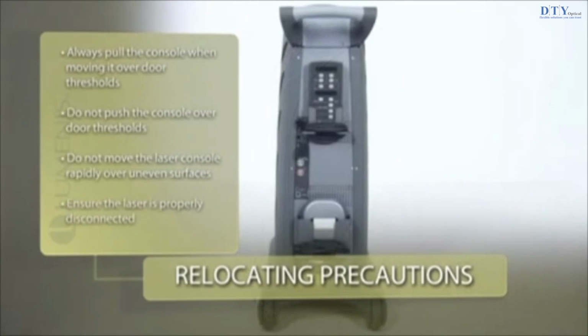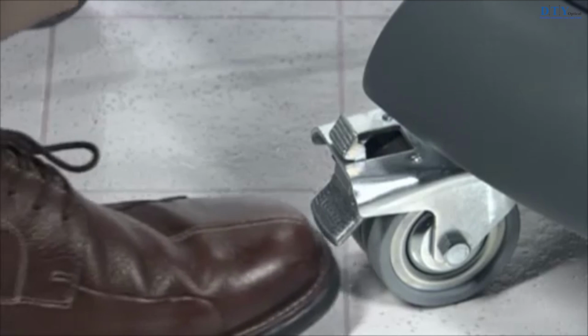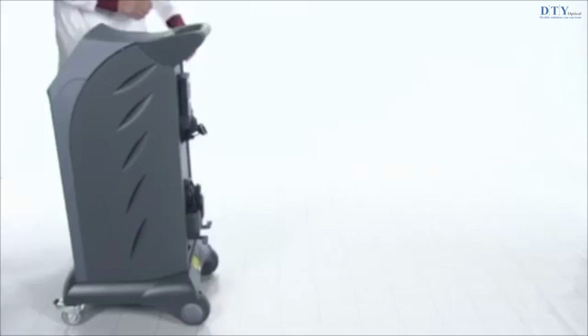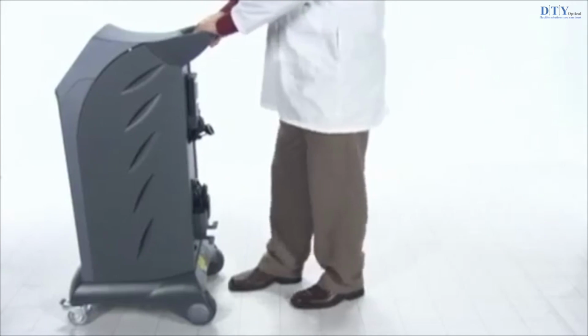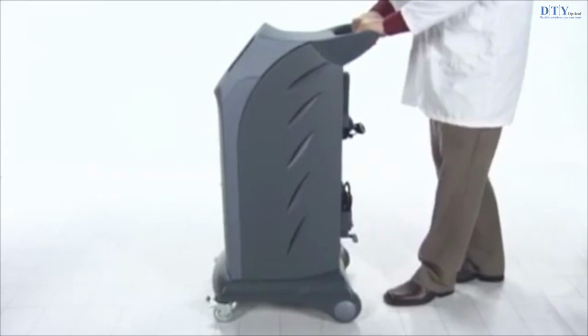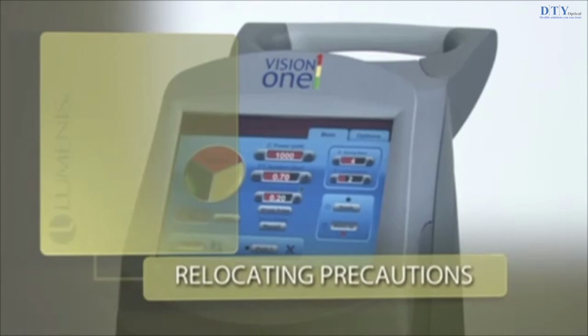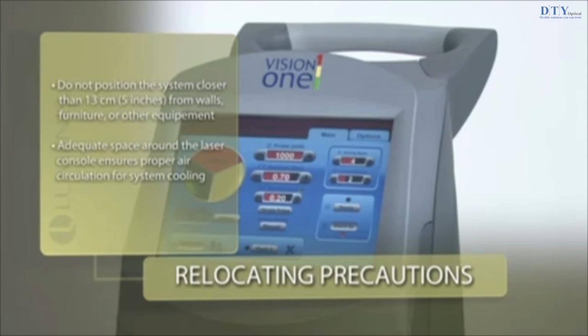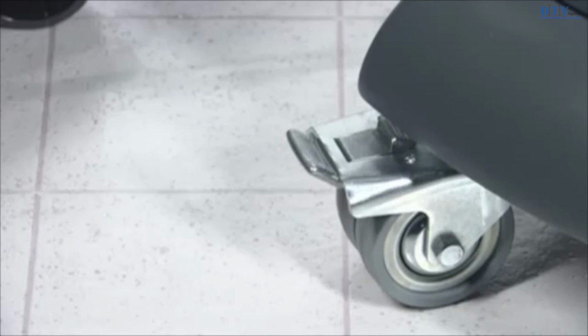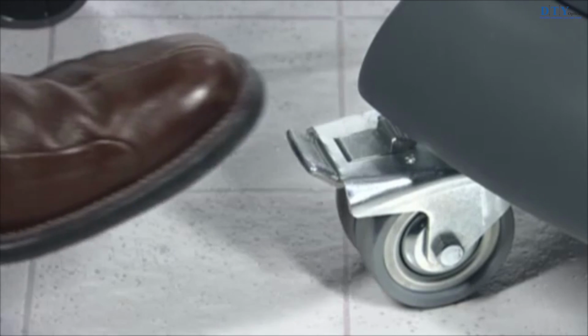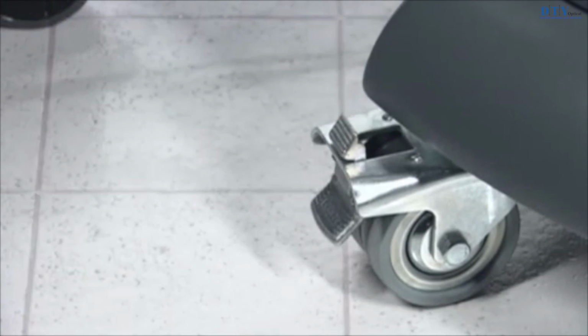When you're ready to move the console, ensure that the laser is properly disconnected as instructed previously. Next, unlock the laser console wheels by pulling up on the front wheel locks and, using the laser console handle, move the laser to the desired site. Do not position the system closer than 13 centimeters, 5 inches from walls, furniture, or other equipment. Adequate space around the laser console ensures proper air circulation for system cooling. Finally, remember to lock the laser console wheels by pressing down on the front wheel locks.